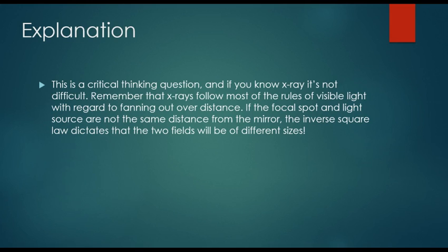given our mechanical constraints, because with these mirrors, sometimes it's really hard for the repairman to get the mirror adjusted to exactly 45 degrees. Or maybe the light bulb socket's a little bit crooked, and that's going to throw off your light field. You may have been at a clinical site where the light field and the X-ray field don't exactly match, and nobody can seem to figure out what the problem is. That's because, if you look in there and it looks like the light bulb socket is perfect, if it's canted by like 1 degree, that can wind up throwing off your light field and make it not match with your X-ray beam.